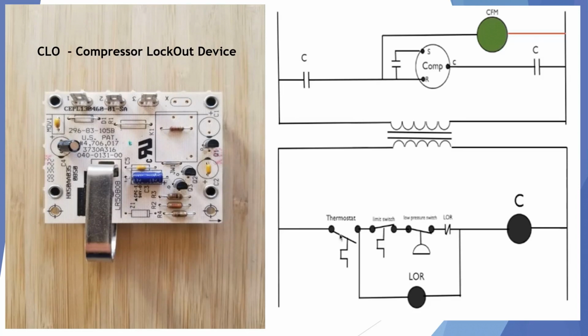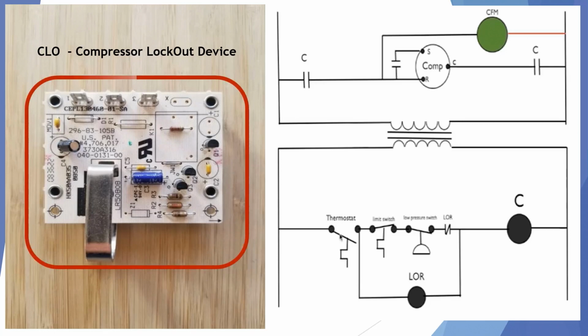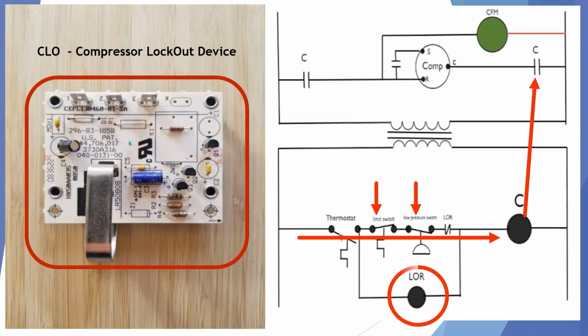Another device that is used by many manufacturers is a CLO, or a compressor or current lockout device. This device is in conjunction with the safety switches so that if a limit switch or a pressure switch opens, it will de-energize the coil to the contactor. The lockout relay will then lock out the system until the power is killed and restored and the pressure or the limit switch situation has been resolved.